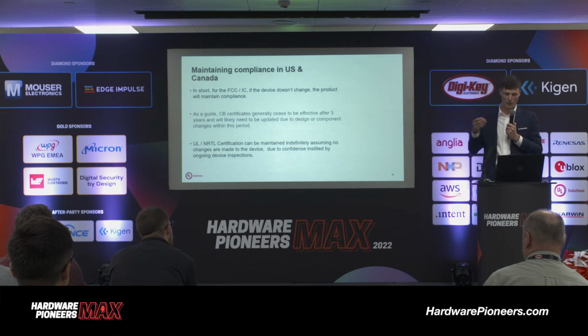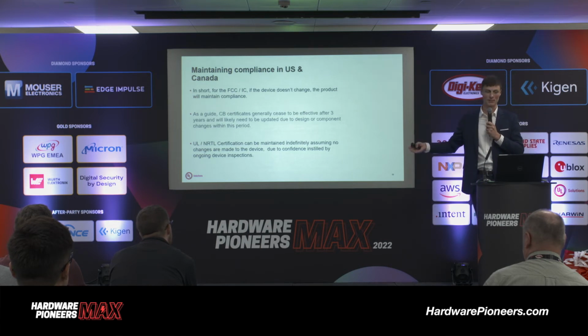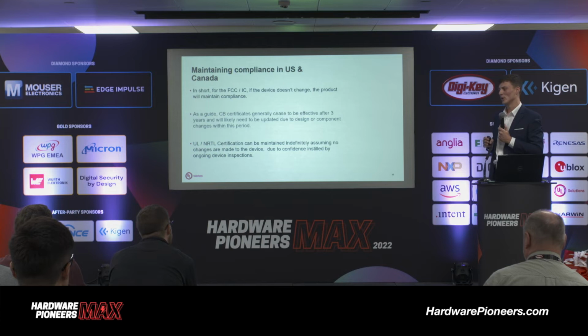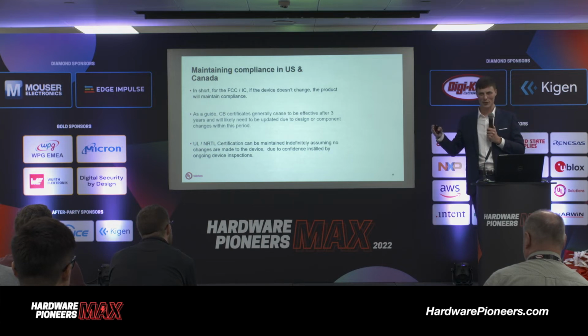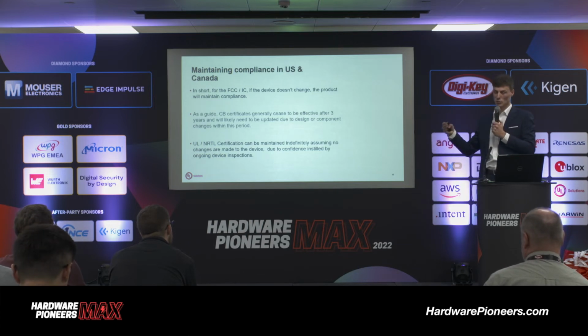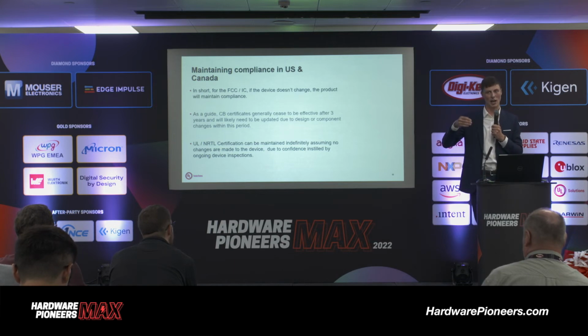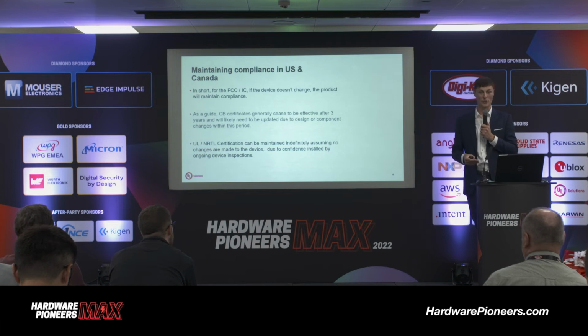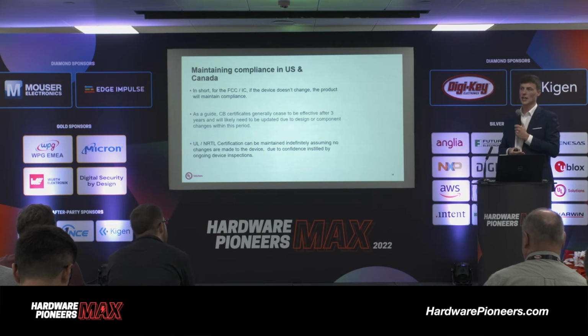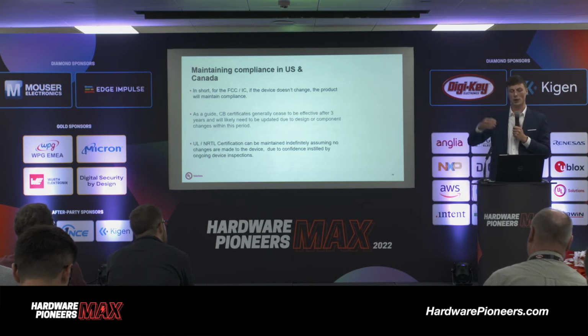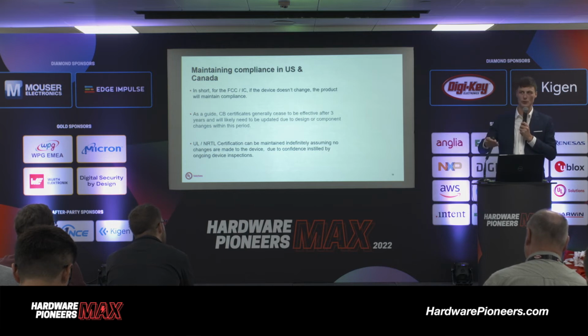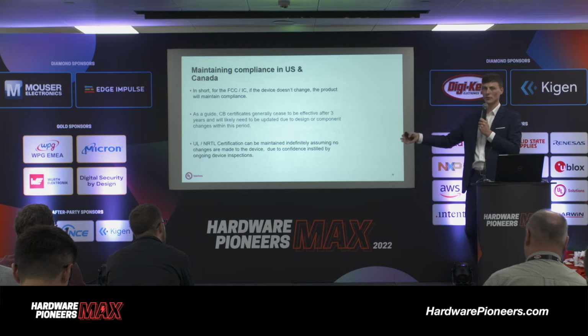However, if you're going globally, you may want to look at what's called the CB scheme, or indeed a UL or NRTL mark for North America. Now, what is the CB scheme? Shortly put, it's a group of countries that have come together and agreed that under certain test practices, and assuming that the components used within the device also hold the CB certification, they will be happy to issue a certificate for that device that will then give you further access to the global market. So it holds a lot more weight than, say, an informative report, because it's had this third-party review by a certification office, and only approved CB test laboratories can issue that evidence of compliance.